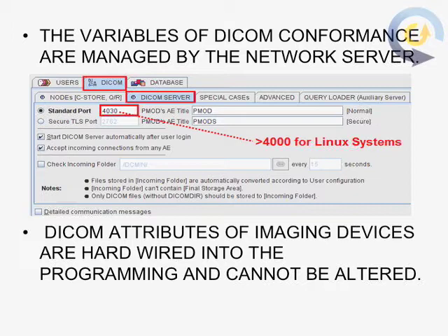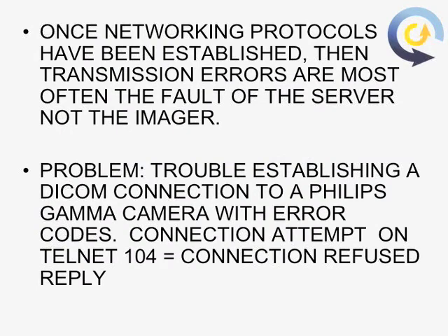The variables of DICOM conformance are managed by the network server. DICOM attributes of imaging devices are hardwired into the programming and cannot be altered. Once networking protocols have been established — IP address, AE titles, etc. — you can see our networking video for more details. Transmission errors are most often the fault of the server and not the imager.